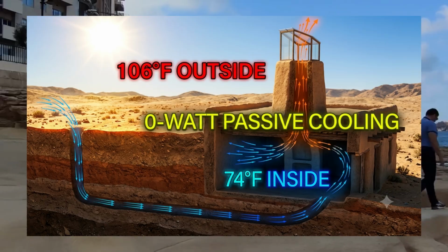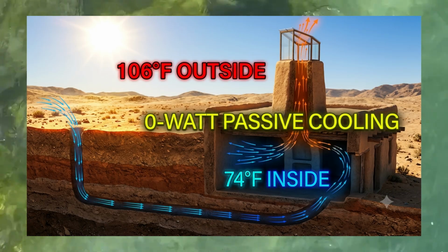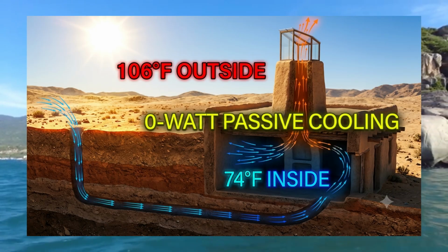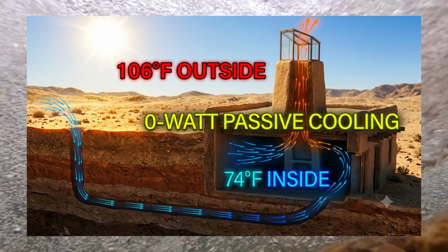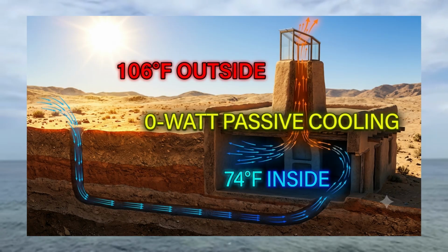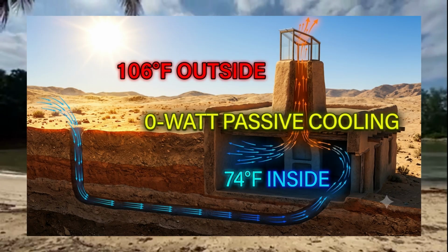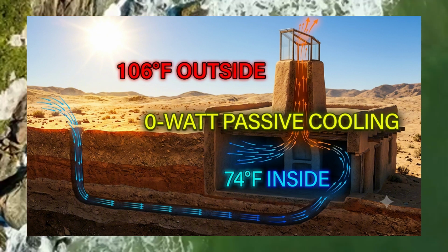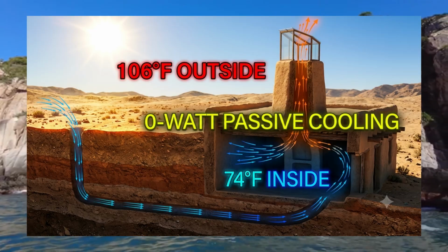The sweet spot for a standard residential layout is a run of approximately 100 feet, sloped gently downward away from the house at a grade of 1%. This slope is critical. It ensures that any condensation that forms as warm air cools down inside the pipe will drain safely into a gravel-filled dry well at the lowest point, preventing mold growth and maintaining clean, fresh air.